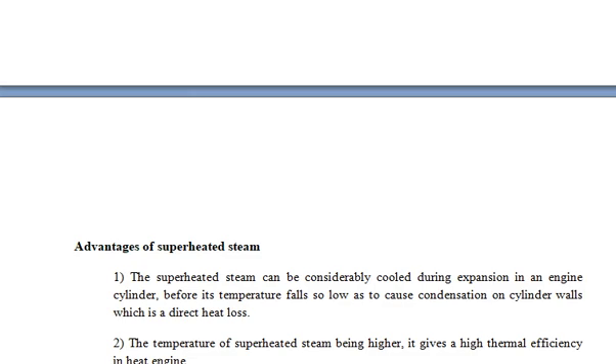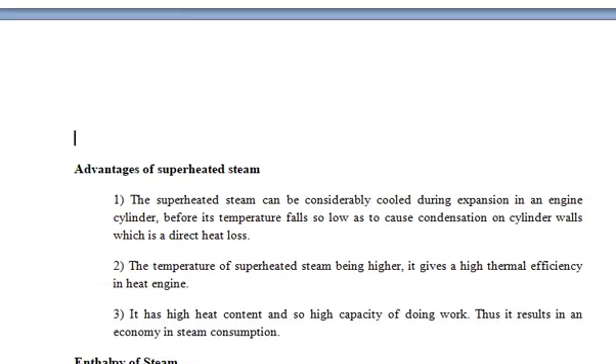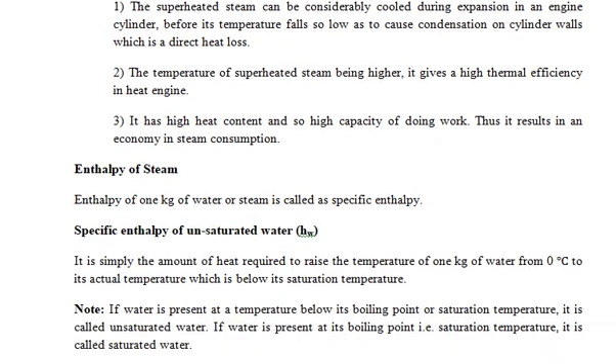Steam has three types: wet steam, dry steam, and superheated steam. The advantages of superheated steam are: first, superheated steam can be considerably cooled during expansion in an engine cylinder before its temperature falls so low as to cause condensation on cylinder walls, which is a direct heat loss. Second, the higher temperature of superheated steam gives higher thermal efficiency. Third, it has a high capacity for doing work, resulting in economy of steam use and minimizing fuel consumption.